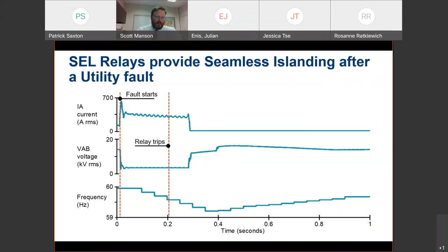The protective relay, about 0.2 seconds later, 0.2 seconds before you can blink your eye, says, uh-oh, that's a fault. Time to isolate. So it says trip. It trips a circuit breaker, which has a mechanical opening time, in this case something less than 100 milliseconds. And you can see the current disappear, extinguish. This is good. The breaker opens. You can see the voltage restore on the microgrid, your VAB voltage restored. Not exactly the nominal, but it gets close.